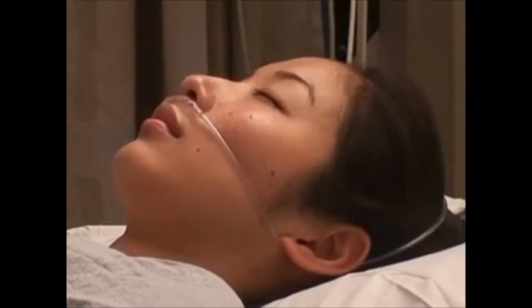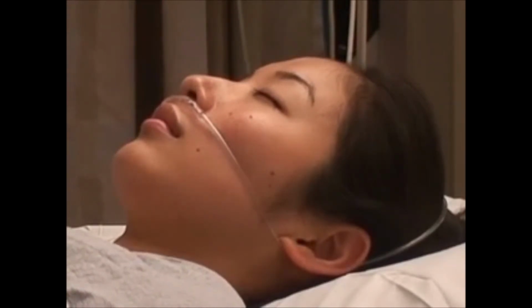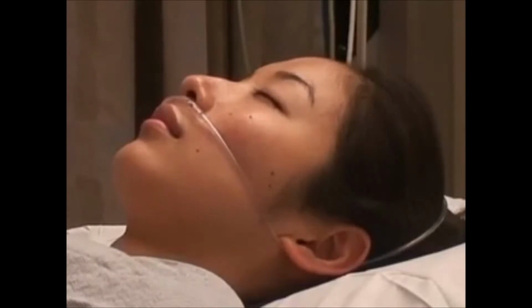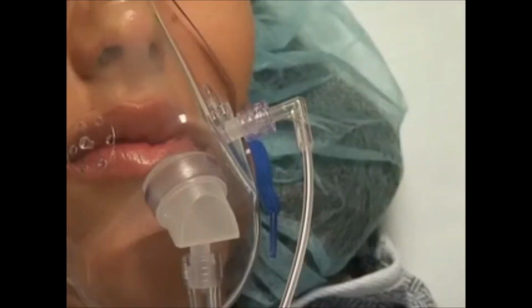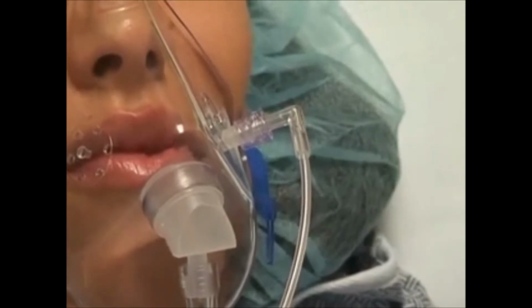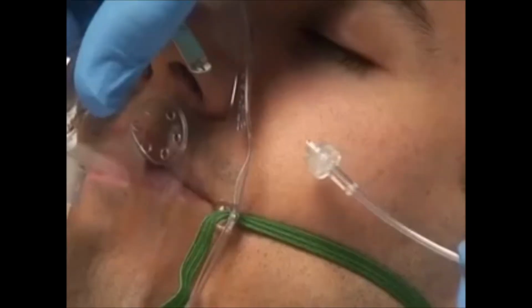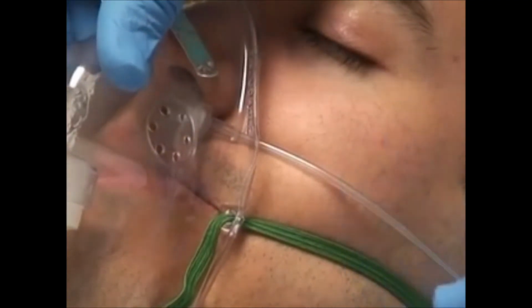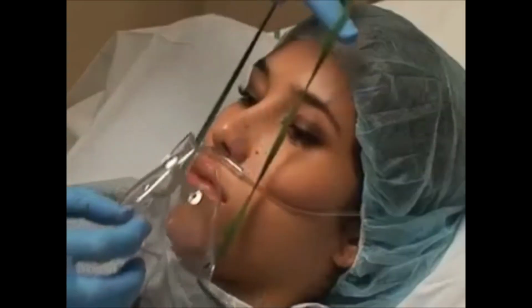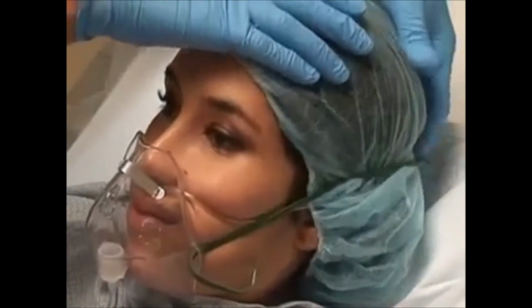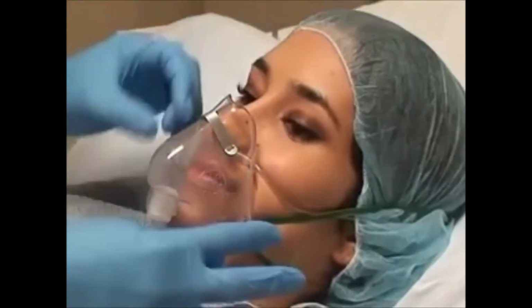However, in patients who are not intubated, side-stream capnographs can be used conveniently with a face mask or nasal cannula to monitor respiration. Nasal cannulas and face masks that feature integrated CO2 sampling are commercially available. You can modify standard face masks by attaching the sampling line directly to the orifice of a mask, or by securing the sampling line inside the mask. Take care that the orifice does not rest against the patient's skin to avoid occlusion of the flow of gas into the sampling line. Alternatively, you can place an integrated sampling nasal cannula underneath a face mask.